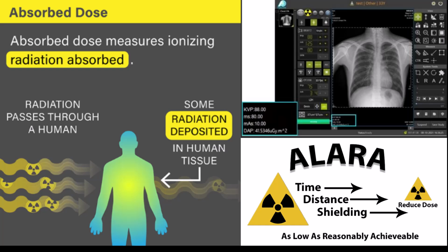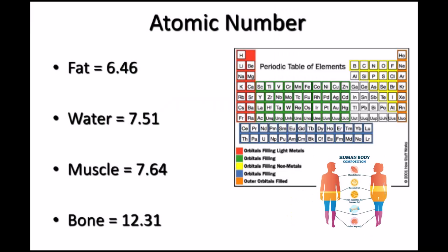Even water is highly attenuating. Typically 10% or less of the primary beam will make it through the patient. To increase the penetration, the X-ray energy should be increased. High Z atomic number materials like bone are more attenuating than water and have an incredibly significant increase in attenuation for lower X-ray energies.